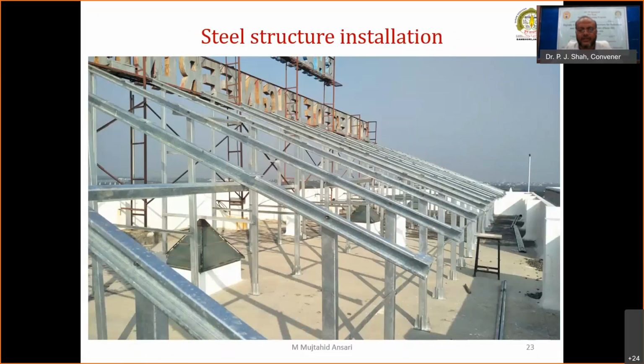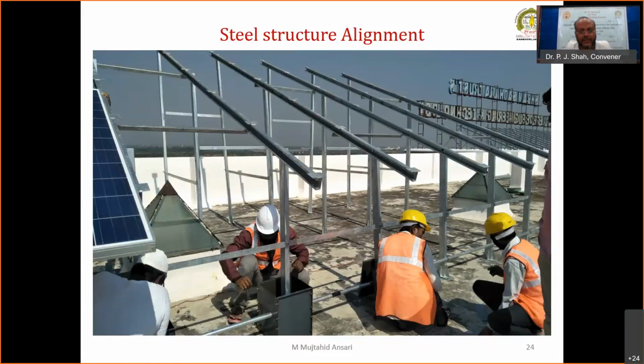So the entire steel structure has been installed with proper alignment, and it is very necessary that we put some of the PV modules before concreting, otherwise it will produce stress on the PV modules. So the final alignment is carried out after alternate installation of PV modules. The new thing we have done is reduce the size of the pedestal by 300 by 300 mm, from the earlier 450 mm by 450 mm. Now the weight of the pedestal decreases.